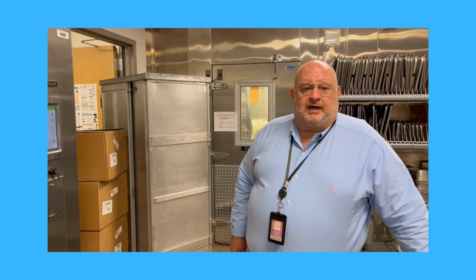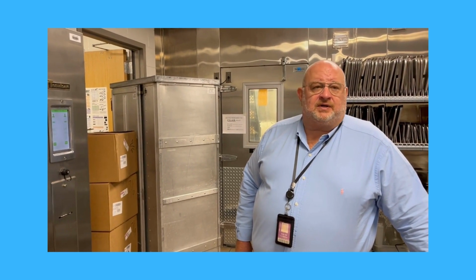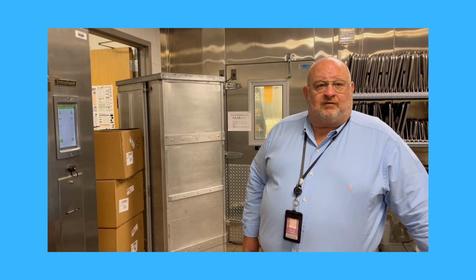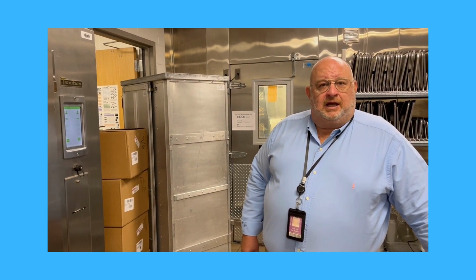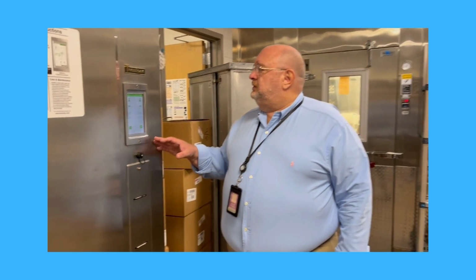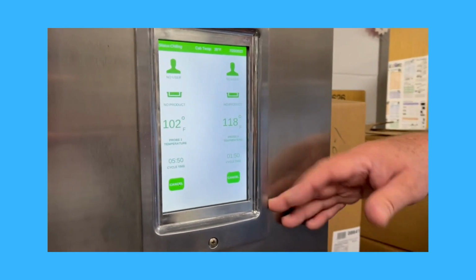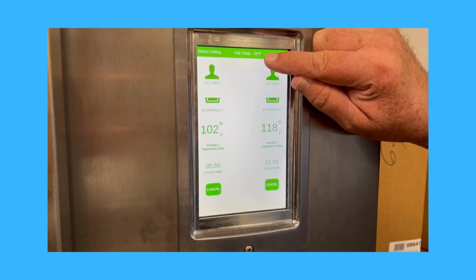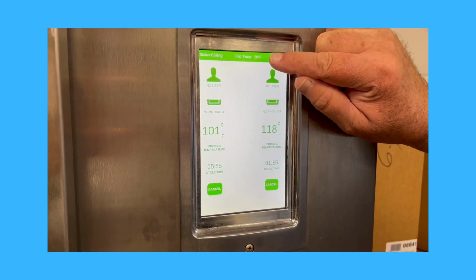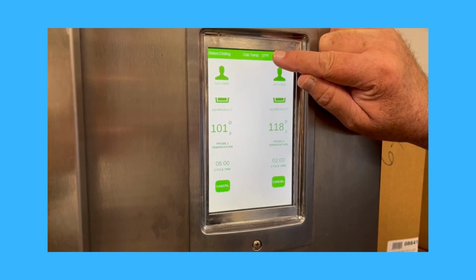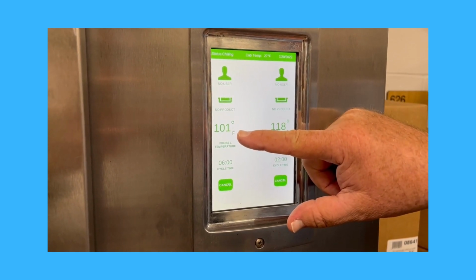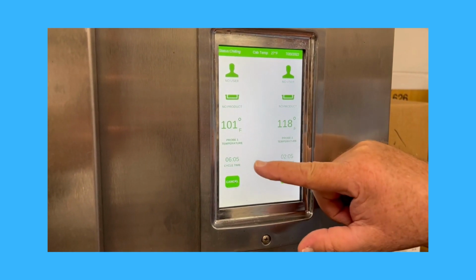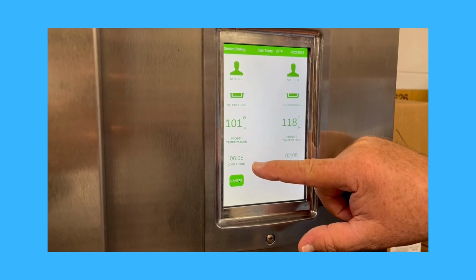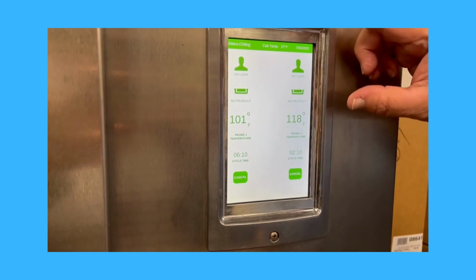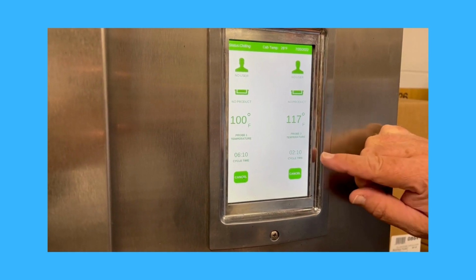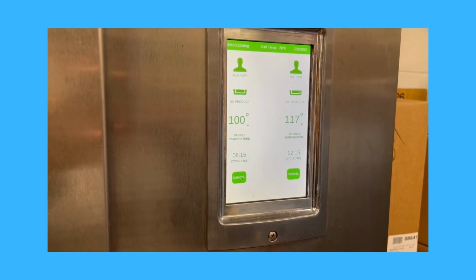Our food is rapidly chilling. We can go about our business in the kitchen, whatever we need to do to close for the day. And when you walk by and you look, there's a couple of things you want to notice. The first is that the cabinet temperature is now down to 28 degrees. It can go below zero, okay? Our first product has gone from 128 to 101 in 6 minutes and 5 seconds. Our second product is now down to 117 after only 2 minutes, 10 seconds.